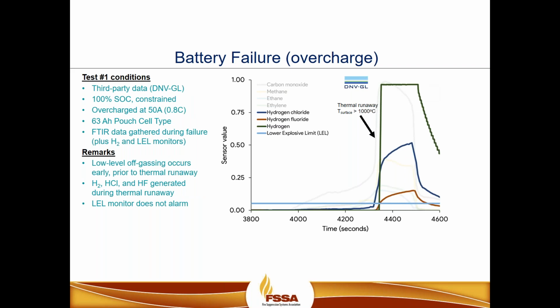Continuing the overcharging event, you'll notice that the additional gases were released after the thermal runaway event occurred. So hydrogen chloride, hydrogen fluoride, and hydrogen were all released into the space through off-gas after thermal runaway had already occurred. But if you see, prior to thermal runaway, this blue line here represents the lower explosive limit. We really wouldn't have been able to get any type of early warning detection from an LEL state until thermal runaway had been achieved.